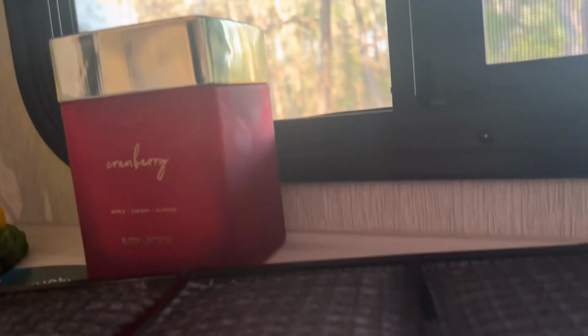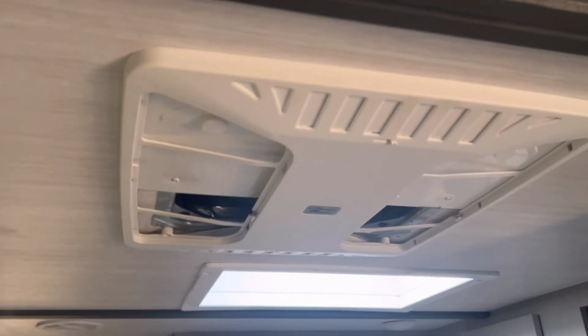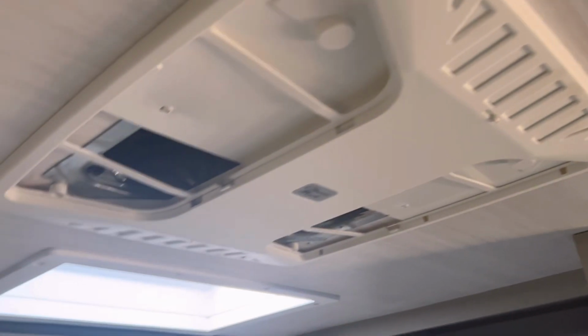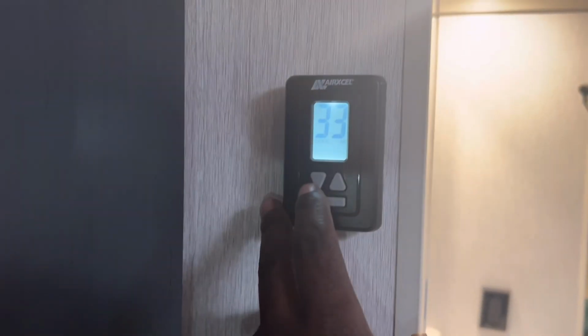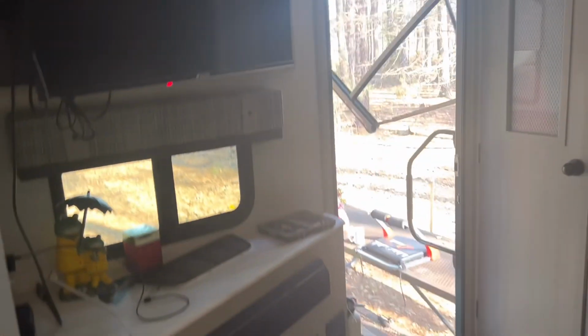So the next item will be the Coleman Mach AC, which is not working. It comes on, but it's not cooling. The compressor never engages. I've had this running while I was diagnosing the slide because it needs to be running for about 15 minutes. I have it on high cool, set at 33 degrees, the lowest setting. Currently it's 64 degrees in here. So now I'll go ahead and start doing my performance test and take down that documentation for this warranty claim.